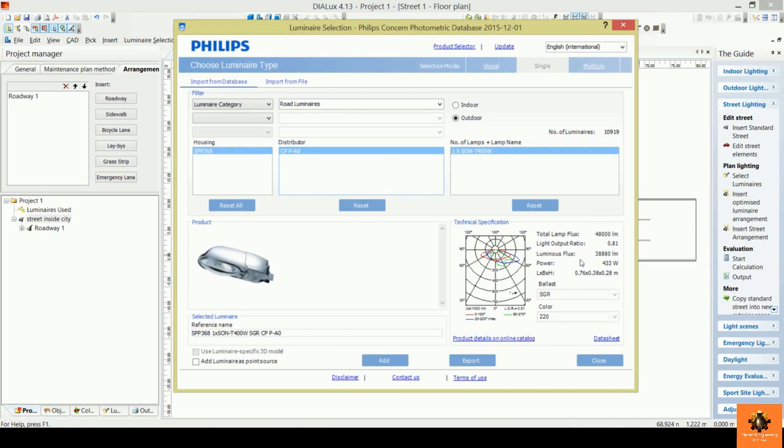And this is the advantage of the LED luminaires, as they consume lower input power. But for that type of pressure sodium luminaire, which has that shape, it consumes larger input power, and you can see its polar curve is more symmetrical, or it has a good polar curve with respect to the LED luminaire polar curve. But you can ask now, from where can we get the datasheet for those street luminaires, or how can we get the variety of the street luminaires which we can select from?